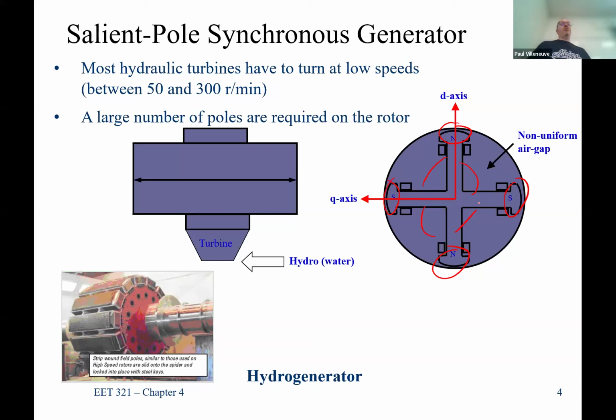Because you need so many poles, it's harder to mill a piece of solid iron to do that, so you build it out of sections instead. Running at slow speed lets you physically make it bigger. This is a round rotor design - you can see on the outer perimeter is where the windings are on the rotor, located about the perimeter.